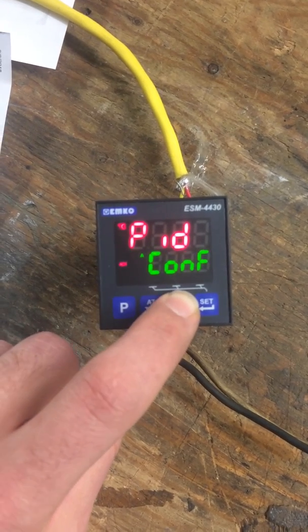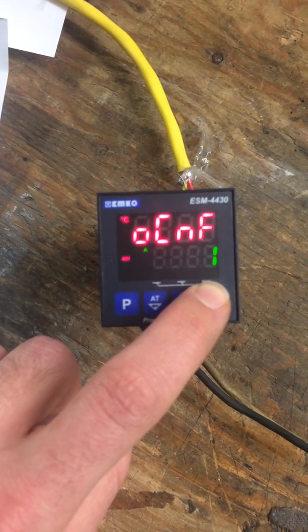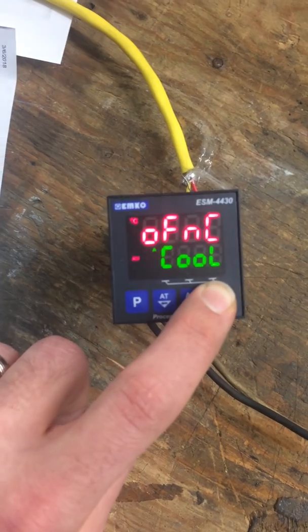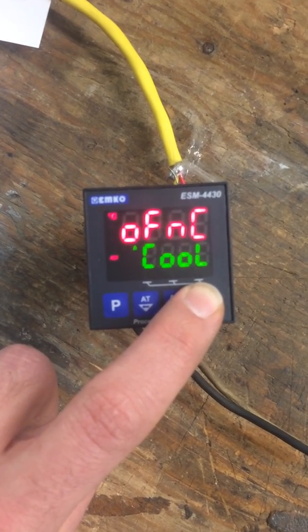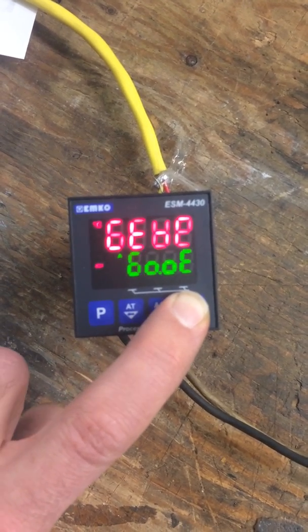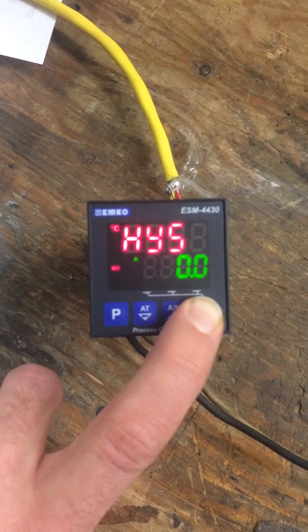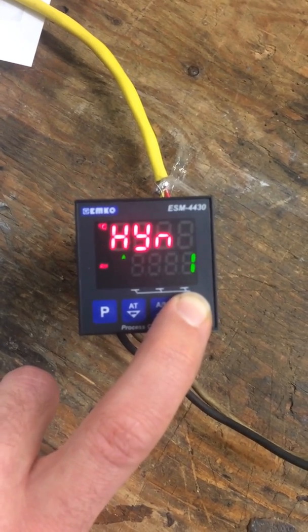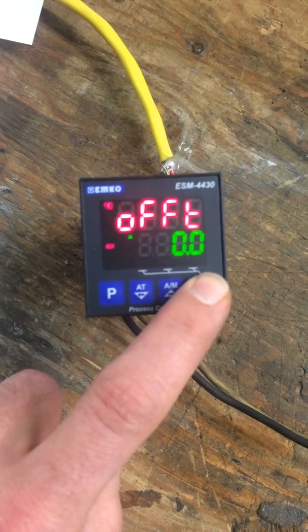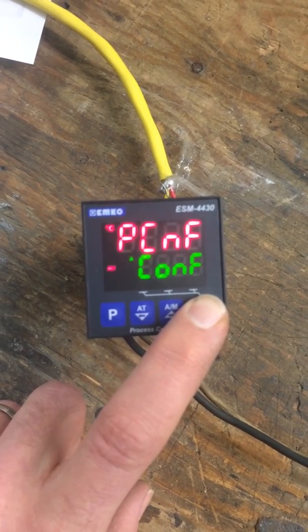PID, we don't adjust — it's on on-off configuration. So we go to the process config. The oFnC function is essentially your output configuration; we don't adjust it, we just leave it as 1. Next is the operation of that function — it should be cooling; it probably comes as default as heat, but it doesn't matter, we don't use it. The next is the control type: on-off — yes, that's correct, instead of PID. Hysteresis: we want to make sure that it's 0 hysteresis, as well as the HYN function, which is hysteresis mode — we leave that as the standard default of number 1. The off time: we don't want a delay in off time, so it's set to 0. And then we're done with this menu.